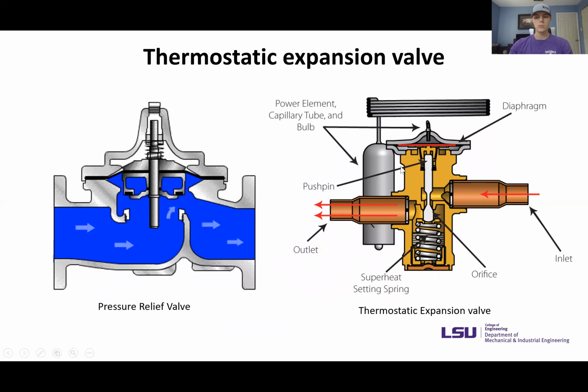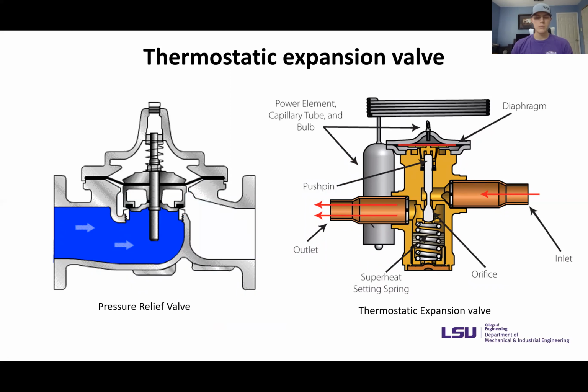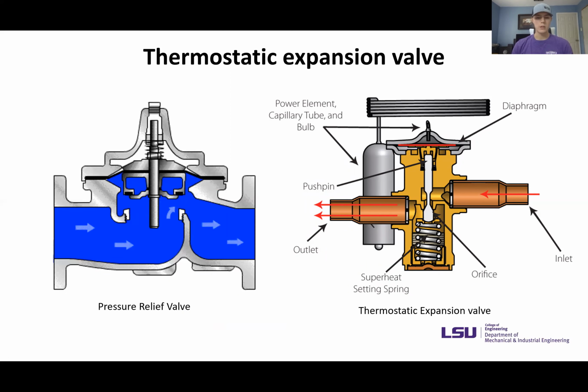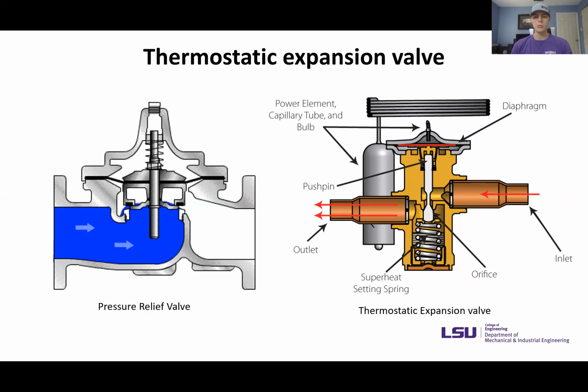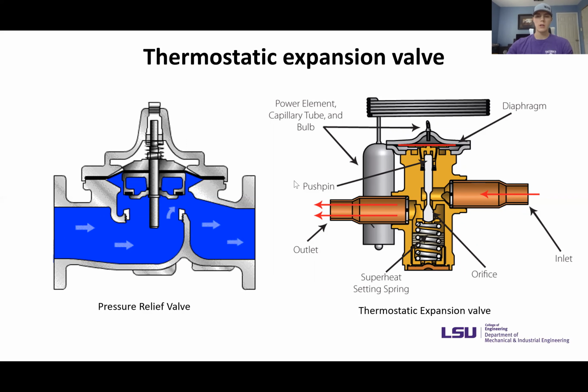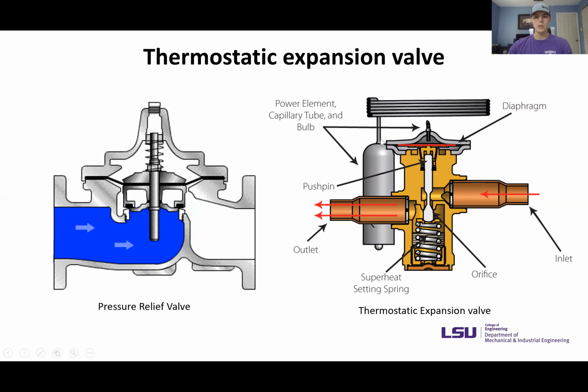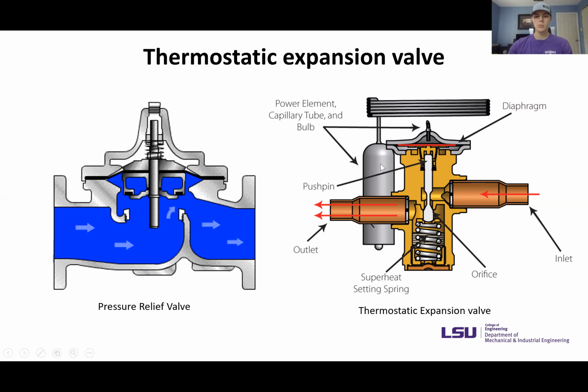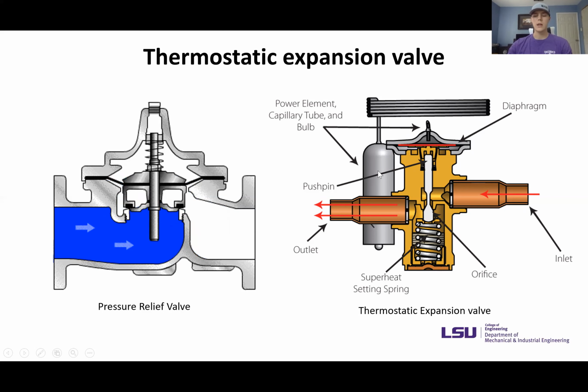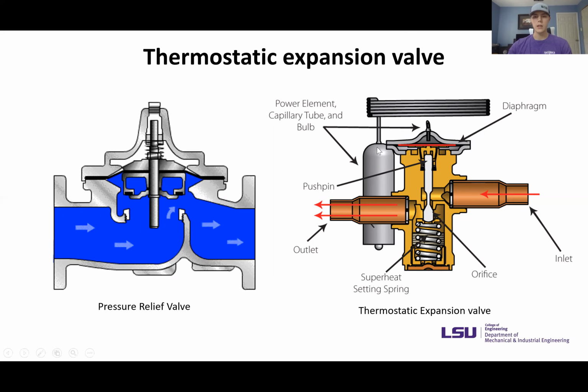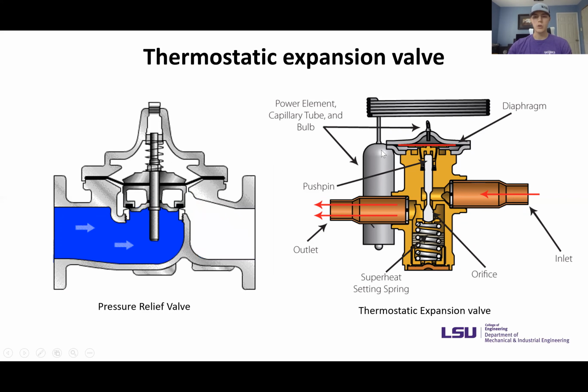Next, we have the thermostatic expansion valve. Now, this valve operates kind of similarly to a pressure relief valve, but it has a couple more components in it. So one of the biggest components is the sensing bulb. The sensing bulb sits at the outlet of the evaporator and detects the superheat. And inside the bulb is refrigerant.